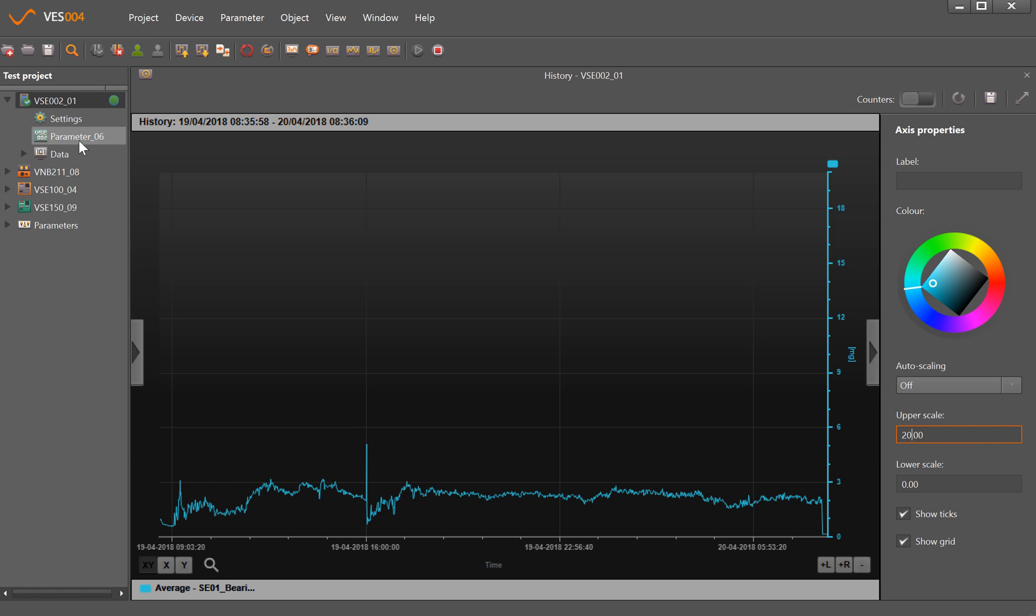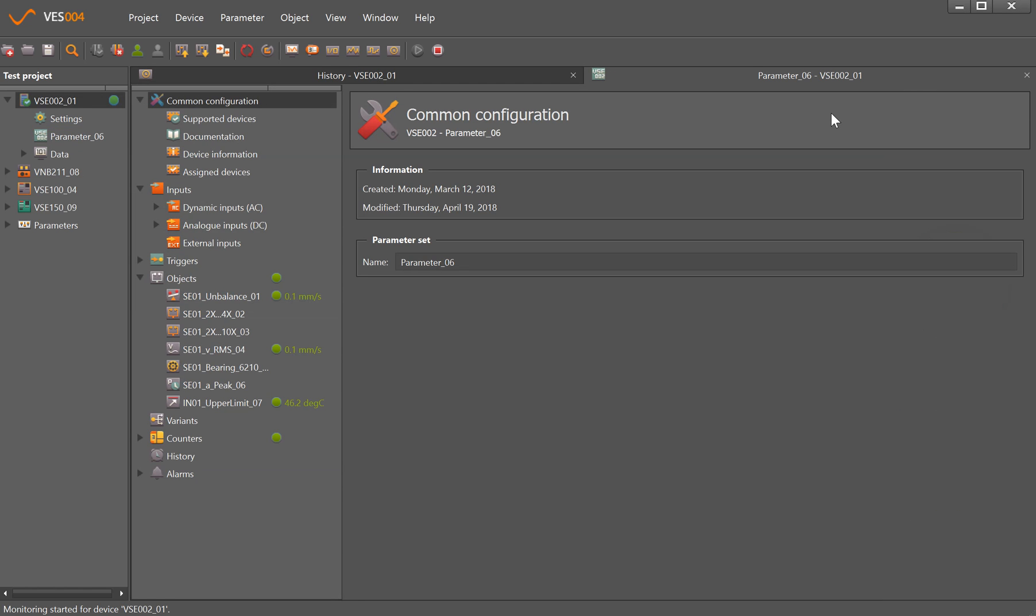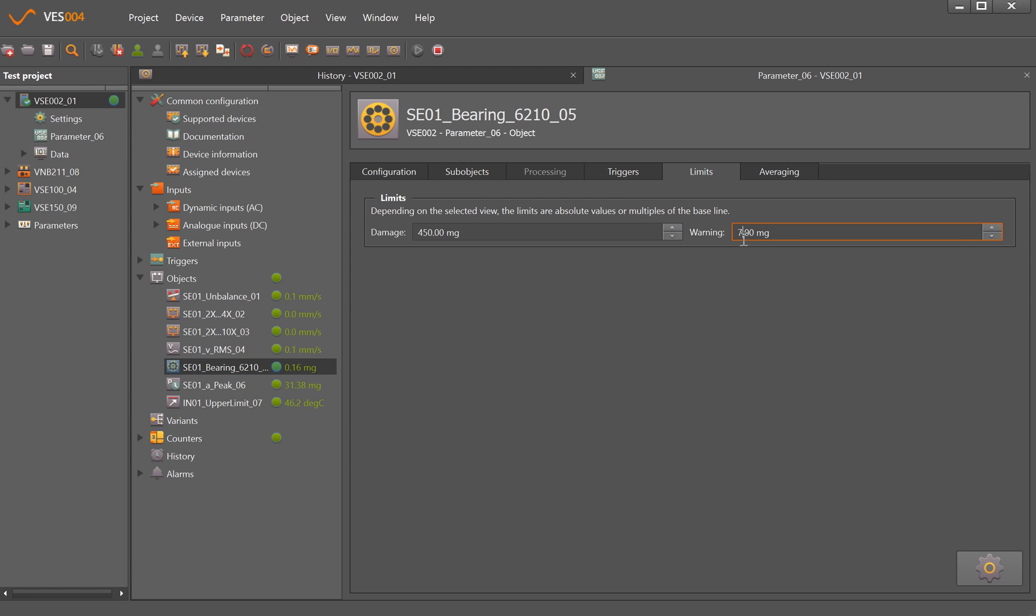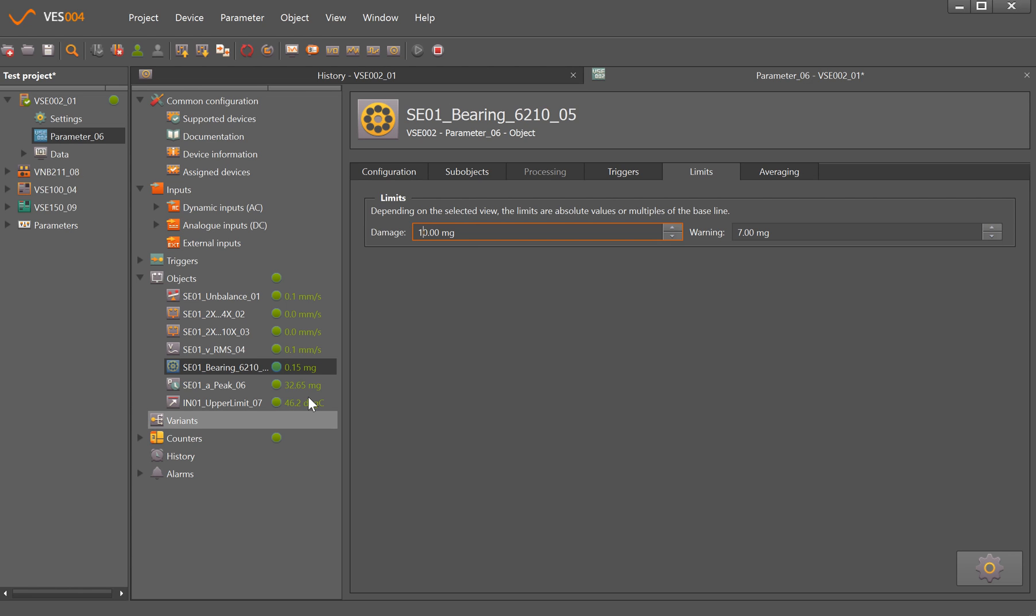So what I want to do is if I go into the parameter set, let's open up this tab here. If I go into where the bearing is, double-click on it, and we have the limits section. So I can just manually type in, say, let's go for 7 and 10 milli g's. So as I've said earlier, this is much lower than you would normally get in industry, but it gives you an idea of what we're doing.